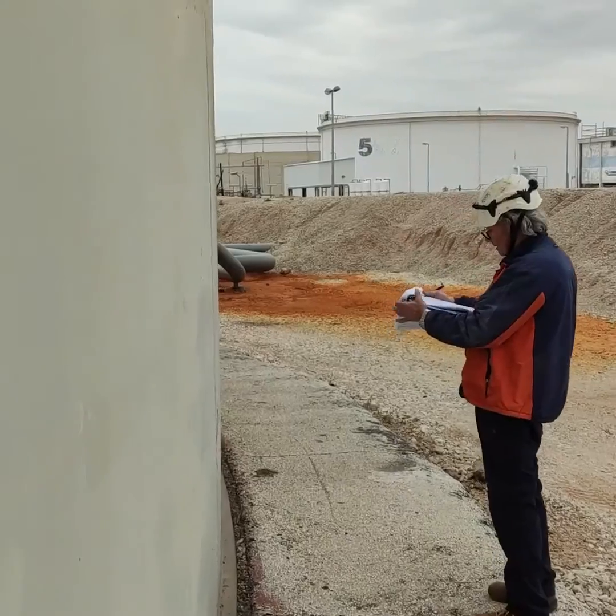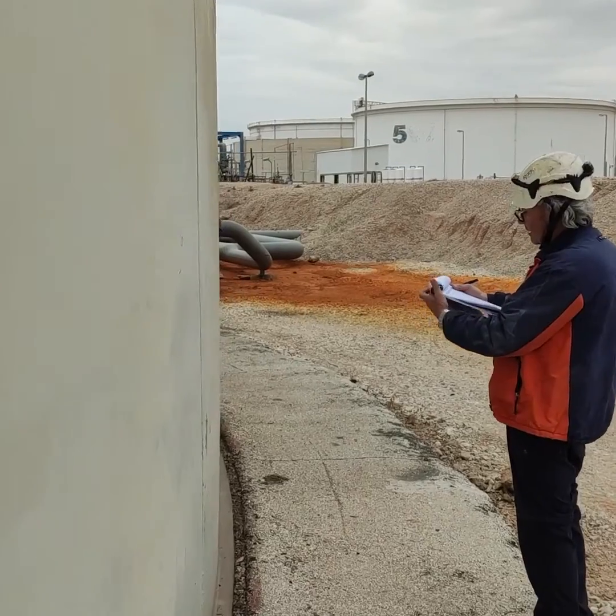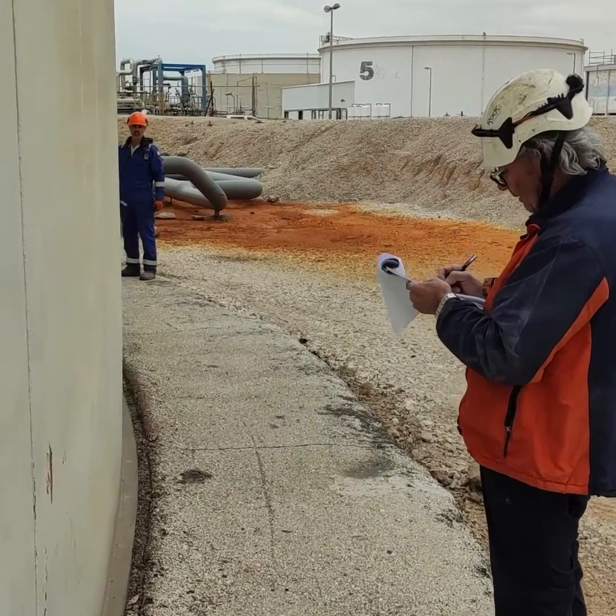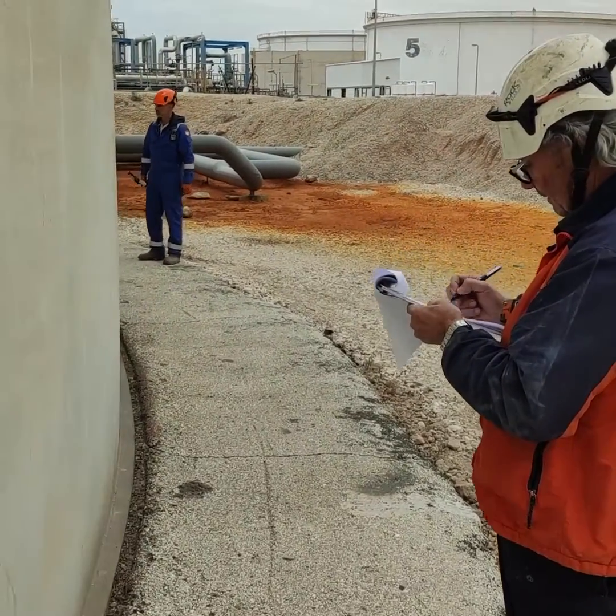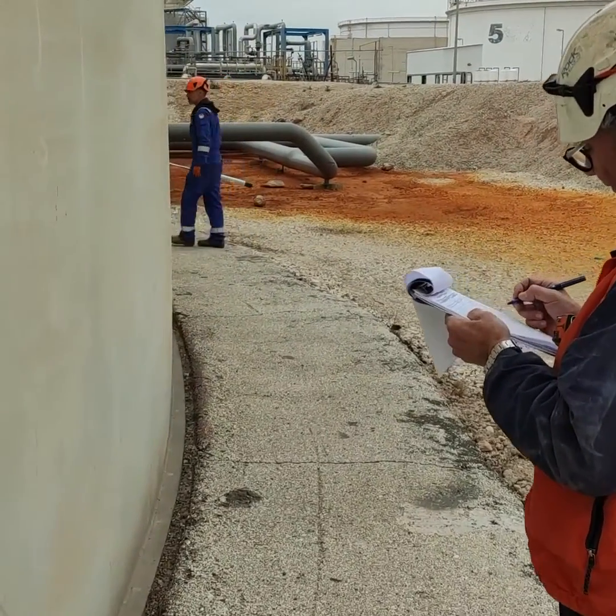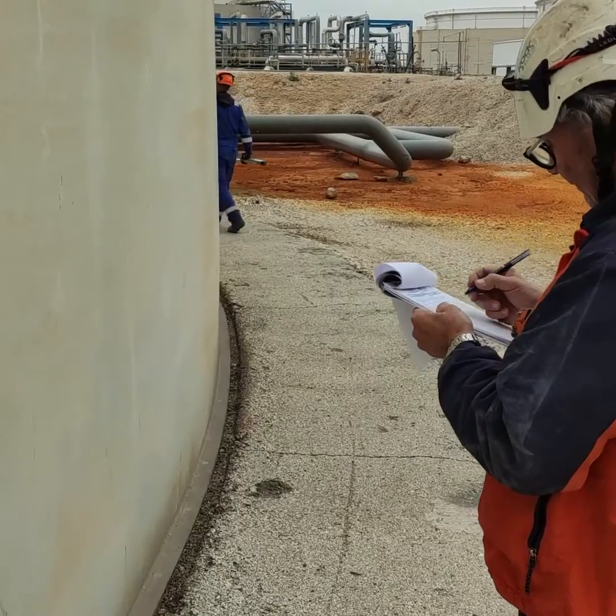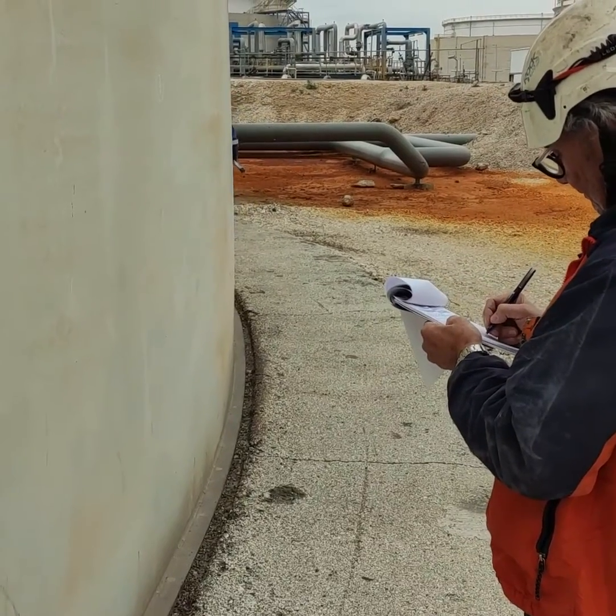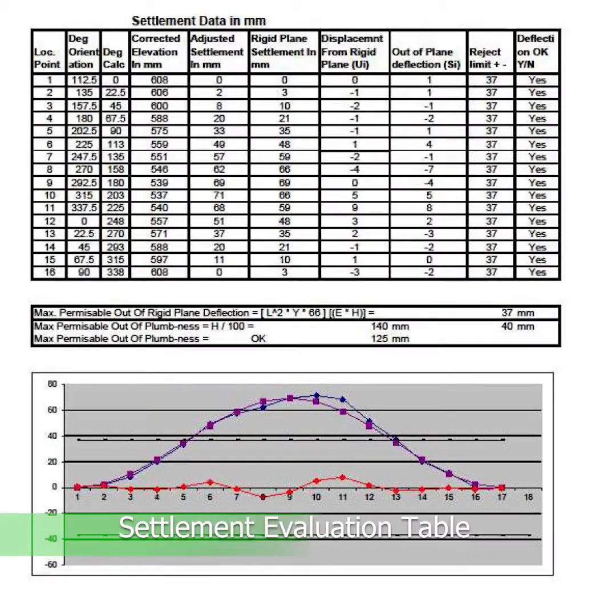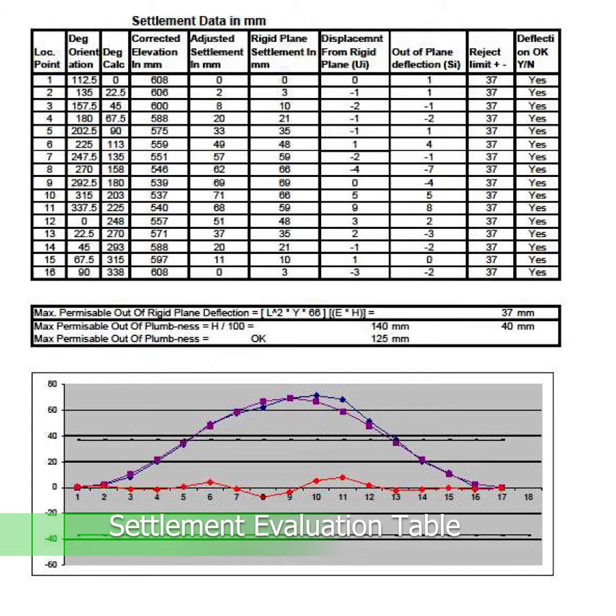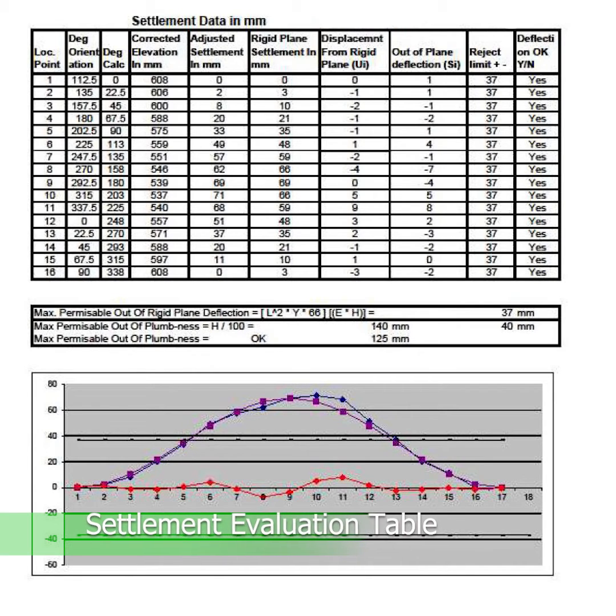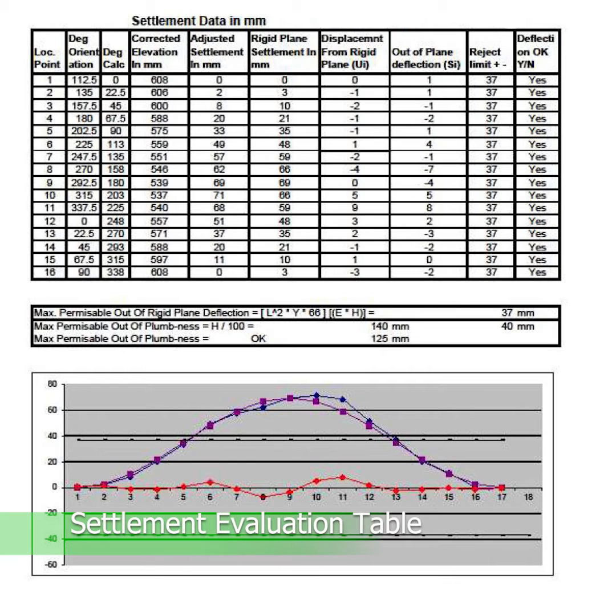The actual settlement is plotted using points around the tank circumference as the abscissa. These data, along with API 653 reference formulas, are used to calculate the plane of rigid tilt settlement and the out-of-plane deflection.